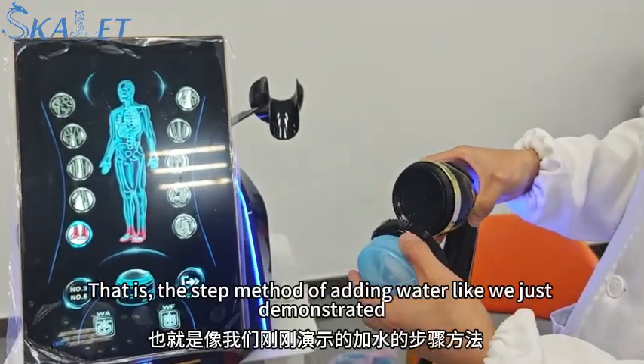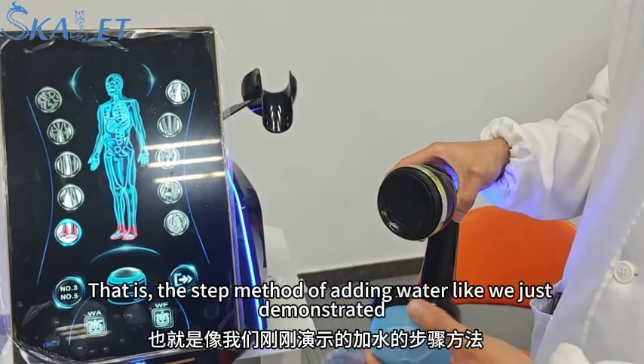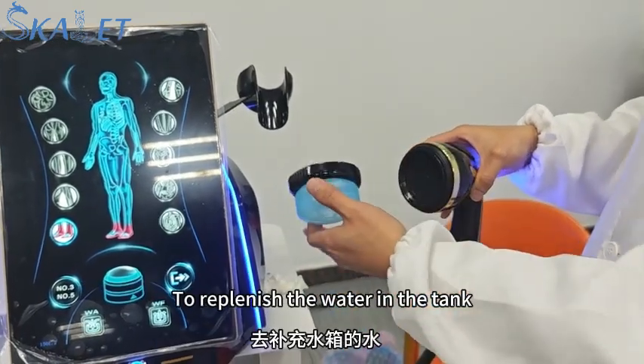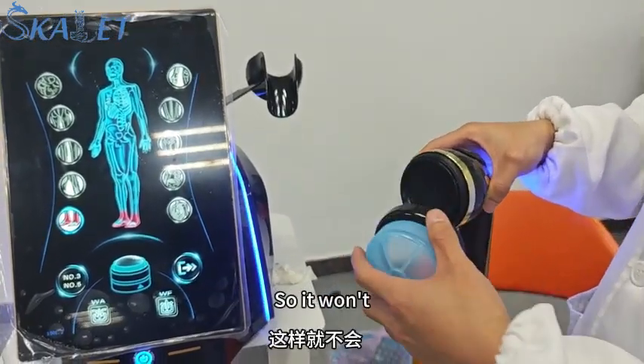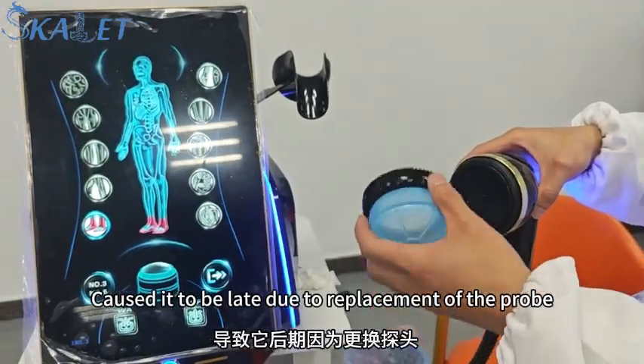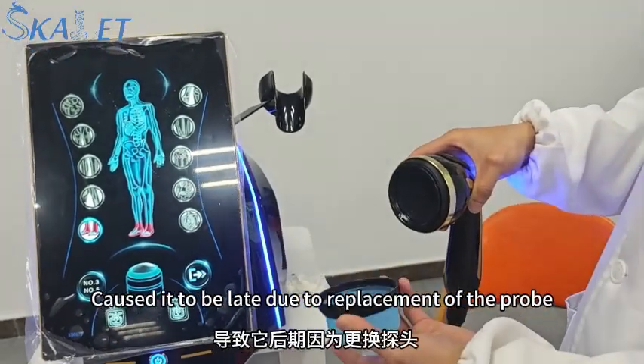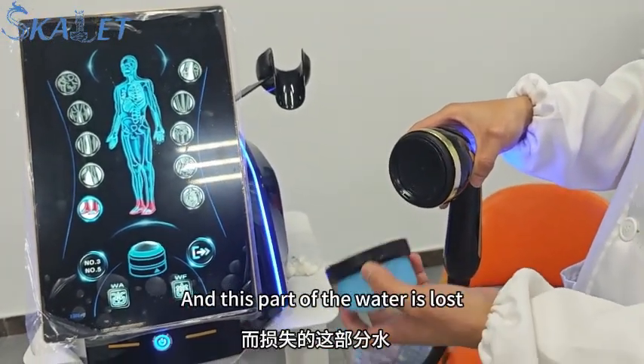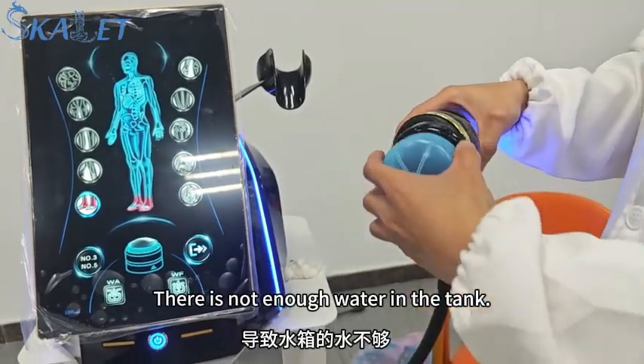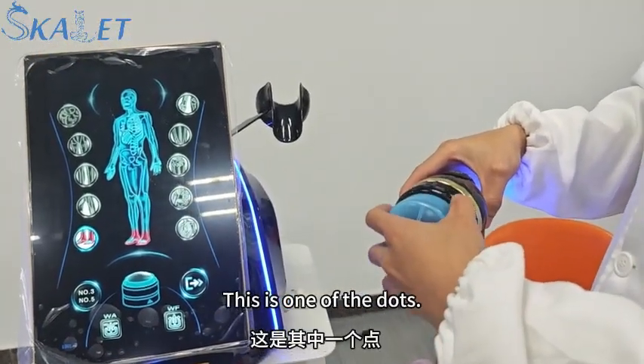That is, the step method of adding water like we just demonstrated, to replenish the water in the tank, so it won't cause there to be not enough water in the tank due to the water lost when replacing the probe. This is one of the key points.